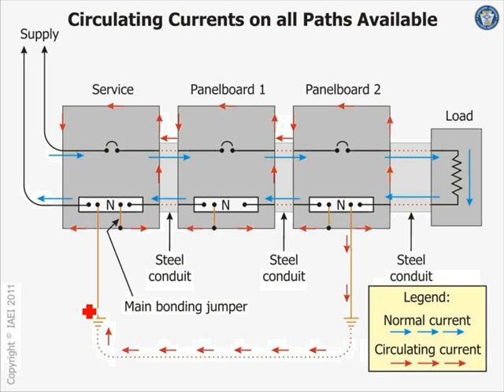So even the current goes right through the earth here. If this is a separate building and you're supposed to create a ground rod right here, a grounding electrode system, you don't bond the neutral again. If you do, then the current will go through the earth. And what's wrong with this? Question would be, what's wrong with this?